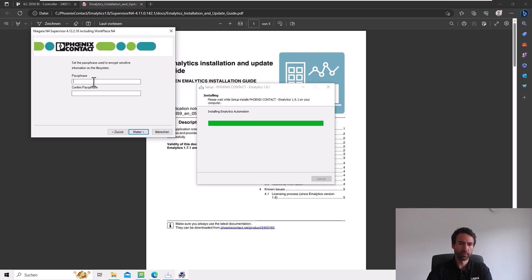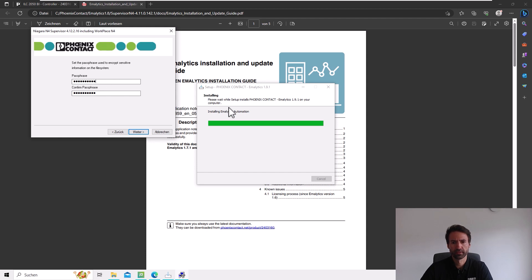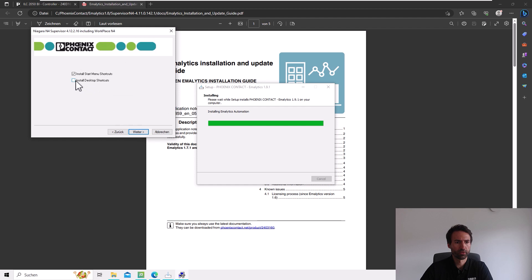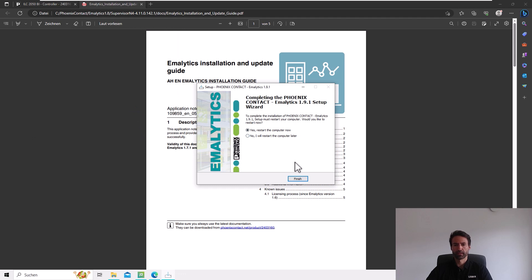It would be helpful if everyone on your team or project has the same passphrase. We must make sure that we don't forget this passphrase, because otherwise we can't copy the station to any other place like a colleague's workbench or a controller. We can now create shortcuts, then install and start the platform daemon — the service which runs in the background, not the workbench. Now we will restart the computer.